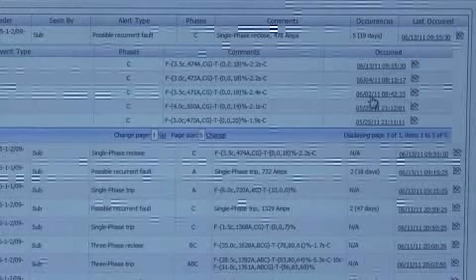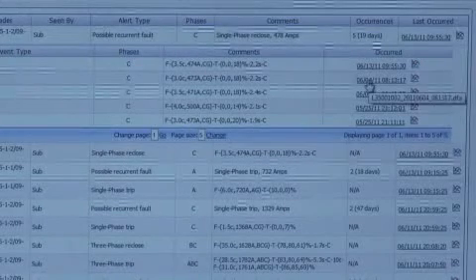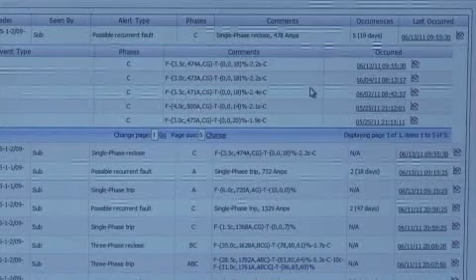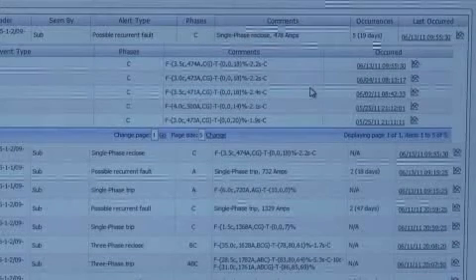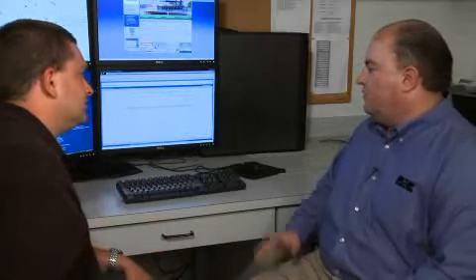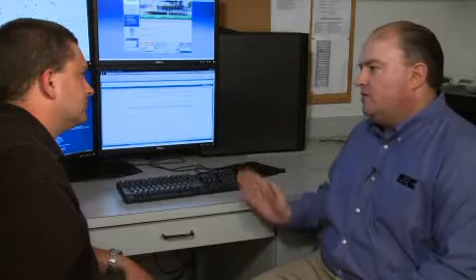But we continued, after the fact, to have three more events — one on June the 2nd, one on June the 4th, and one on June the 13th. This is something that we want to know about because this is a fault that perhaps we can go out there and find and maybe prevent an outage. Now, if you did not have the DFA, would you know that this is happening? Most likely we would not unless a customer called, and we haven't had any calls on this particular event.